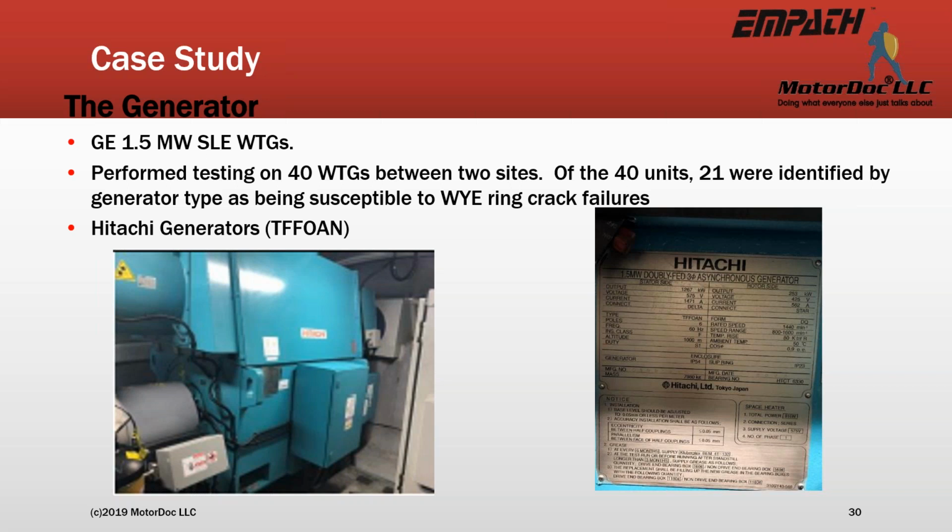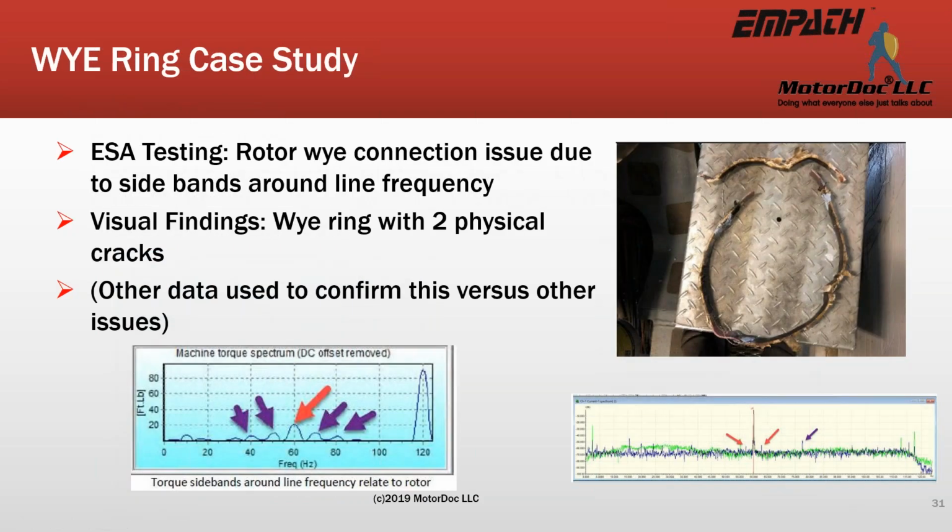We went up there and set aside 5 days. A day and a half into being there, with half of one of the days having no wind, we had completed both sites. Then we came back and we had identified 21 that had issues. So they brought in Delhomme from Quebec, and Delhomme came in and replaced the Y rings and recorded what their findings were.